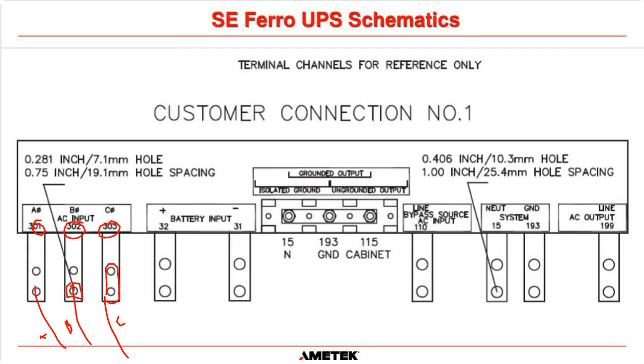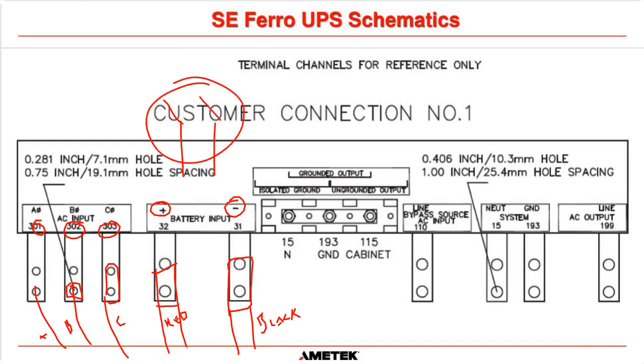The battery input. Now, this is extremely important. Positive and minus. So you should connect your battery positive, which should be a red cable, but don't trust the cable color. Okay. Always, when you are connecting up a battery to a system for the first time, obviously this one here should be black. Remember, we have a breaker up here. So you can connect these 2 cables without worrying as long as that breaker is open. But what you need to do is you need to get a multimeter, and you need to put your positive cable from your multimeter here, your black or negative cable from your multimeter here, and you need to check with that meter that the polarity is correct.